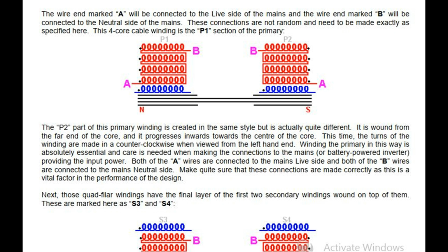The P2 part of this primary winding is created in the same style but is actually quite different. It is wound from the far end of the core, and it progresses inwards towards the center of the core. This time, the turns of the winding are made in a counterclockwise direction when viewed from the left-hand end. Winding the primary in this way is absolutely essential and care is needed when making the connections to the mains, or battery-powered inverter, providing the input power.